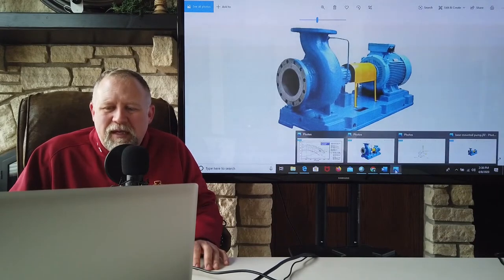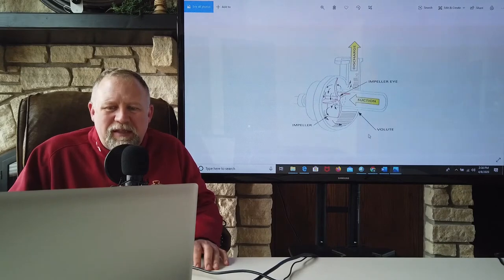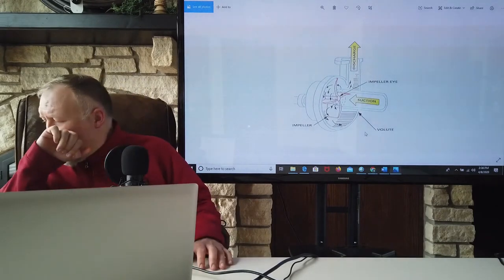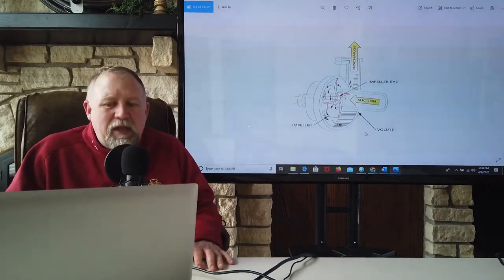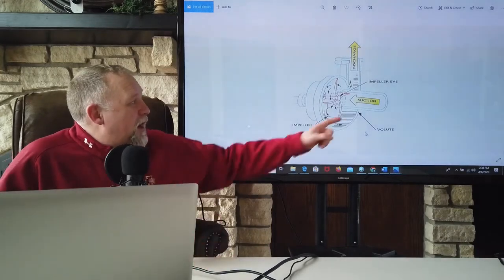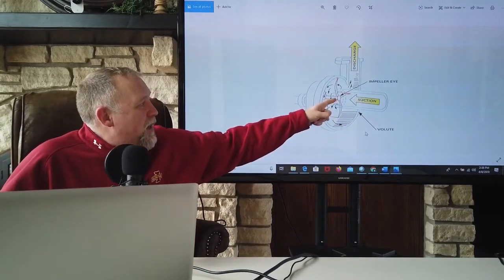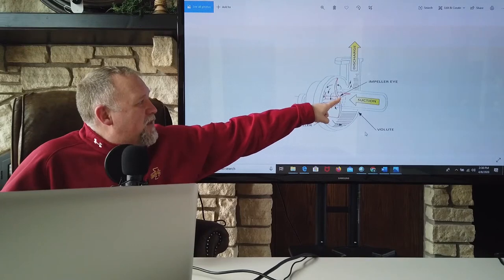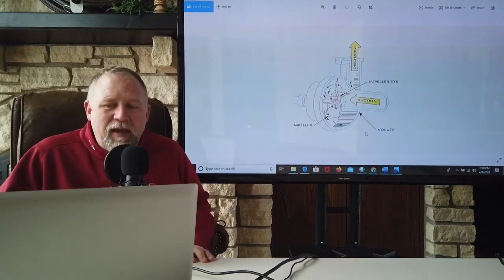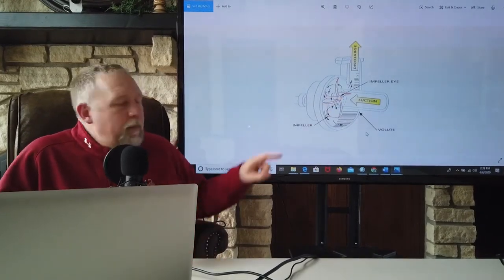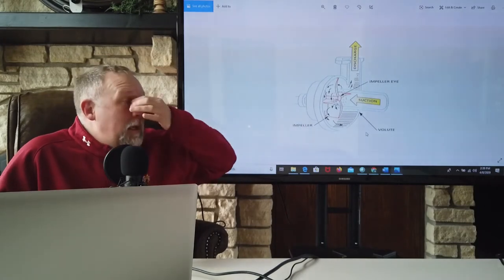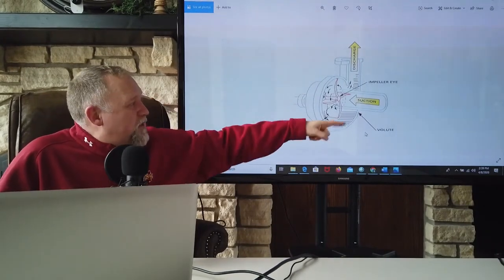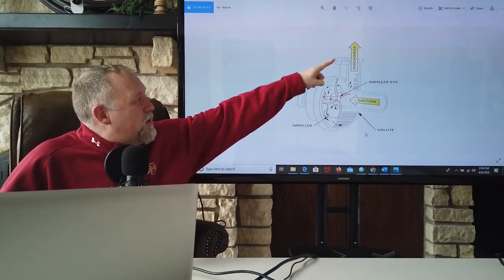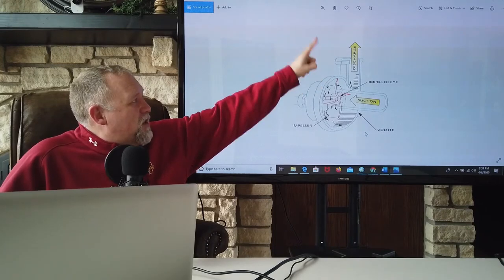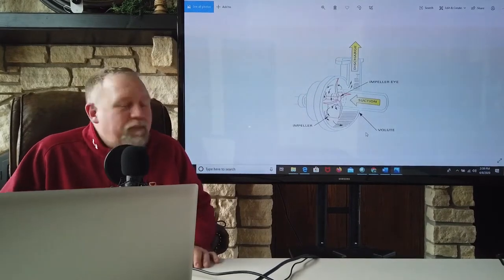All right, now let's take a look at some of the other pictures. So this is just a drawing of what I just described, the suction going into the impeller. The center of that impeller is going to be called the impeller eye. The impeller spins round and round and forces the water out the discharge and down the pipe.